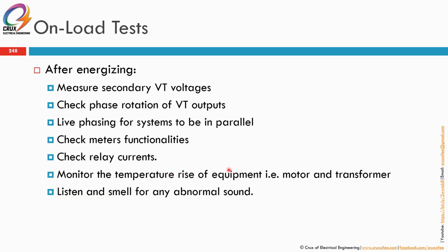Then on-load test after energizing. This is once you've done all the high pot, the insulation test, then do the functional test, and the electrical service contractor with the electrical service engineer, they bring you the form H as per electrical regulation 94. So the form H will be signed by the electrical service contractor, telling you that the equipment or the electrical system is safe to be energized after all these tests have been done.